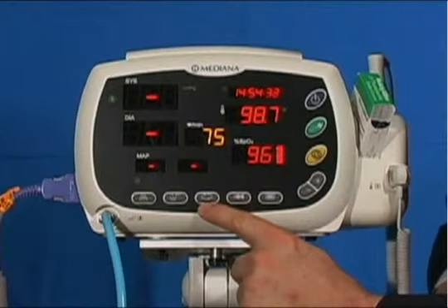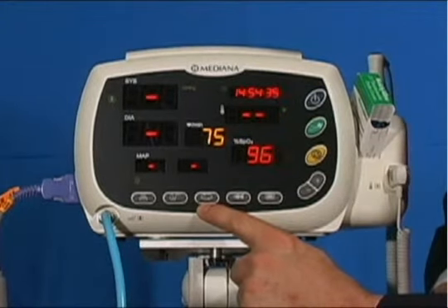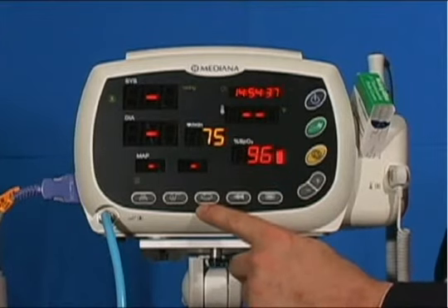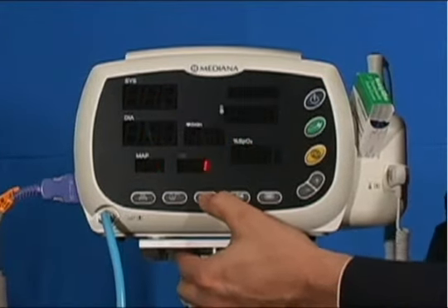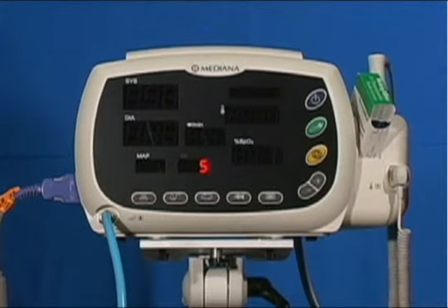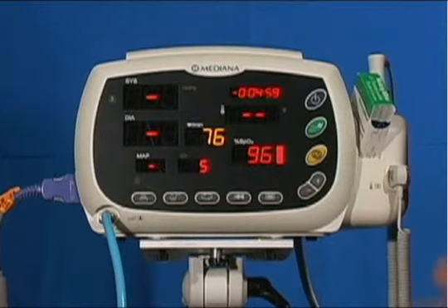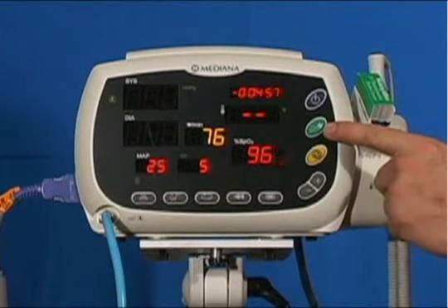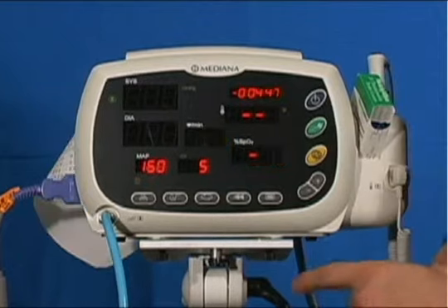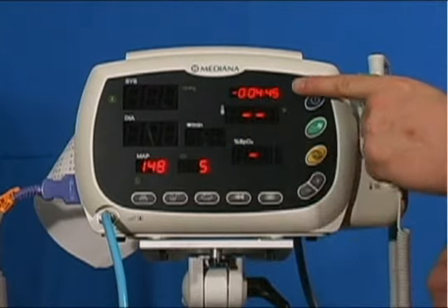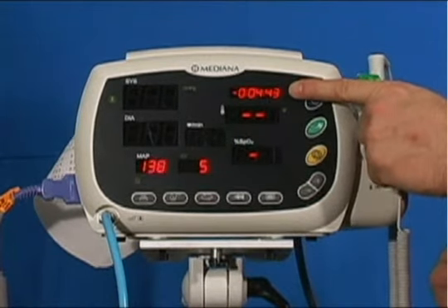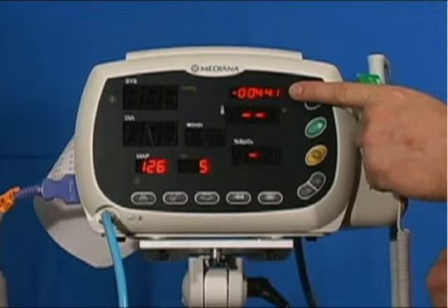The interval button, let's say I want to change the interval to every 5 minutes. I just press it. When I get to 5, I leave it. After about 3 seconds, it automatically initiates that interval, and it stays on the 5-minute interval until I press the green button again. When it goes into the interval mode, the clock here starts a countdown, so that it automatically tells you when it's going to cycle another blood pressure.